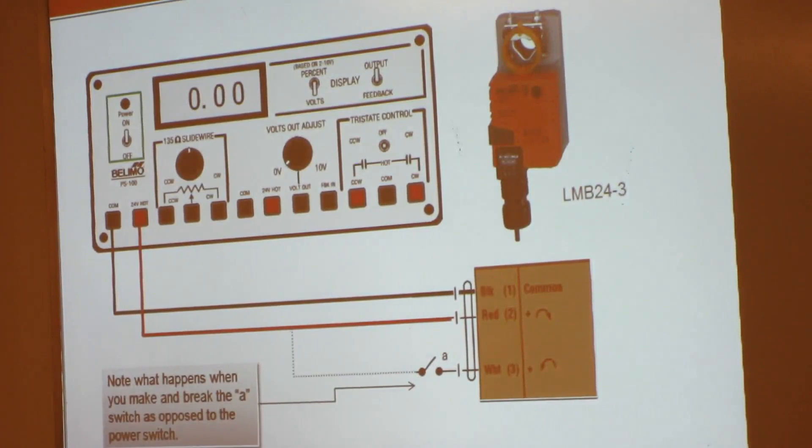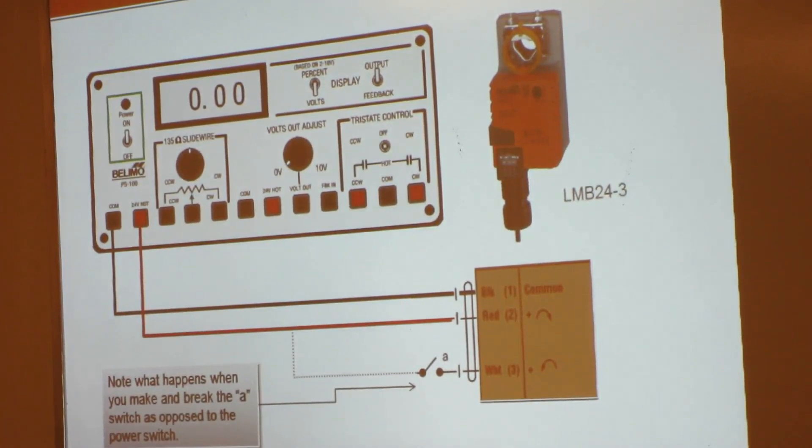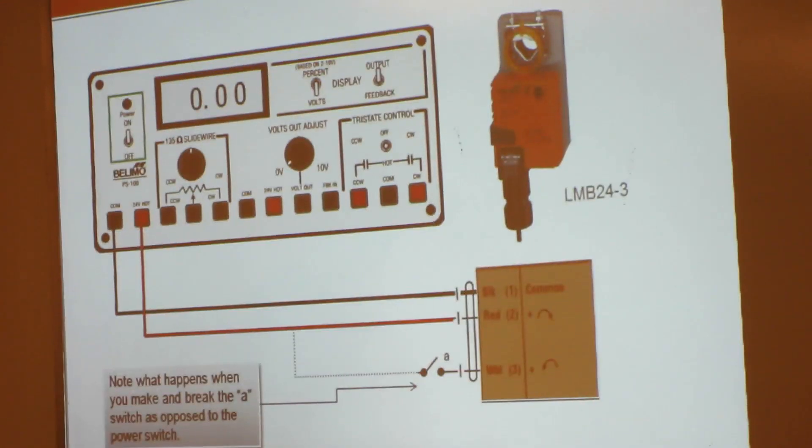If you have it wired up, apply power and let's see what happens. These are LMB24-3 actuators. Anybody want to tell me what that means? LMB24-3 — the dash three means on, off, or floating. Non-spring — there's a B, not an F, in that part of the model number.